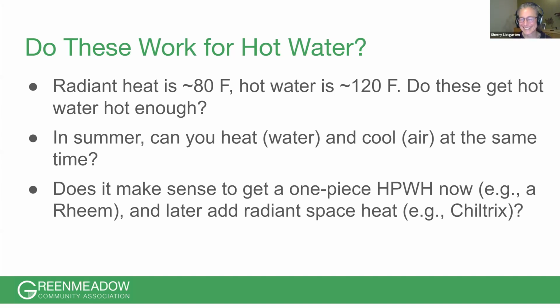Yeah, go ahead. Well, I just want to make this clear to our customers: most heat pump water heaters all come from the same plant in China, so I can say categorically, they're all the same. On low speed they only make around 3,800 BTUs an hour, and on high speed, like 5,500 BTUs an hour. So when we're used to having a 30,000 or 40,000 BTU water heater, this is a drop in the bucket. I did a little calculation last night, or was it over the weekend? At 3,800 BTUs an hour, it takes like 6.7 hours to move it from 60 degrees to 120 degrees.